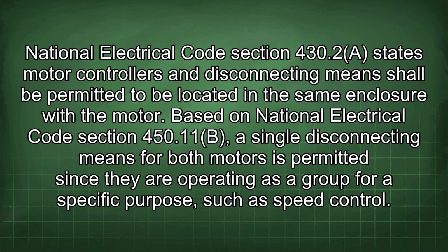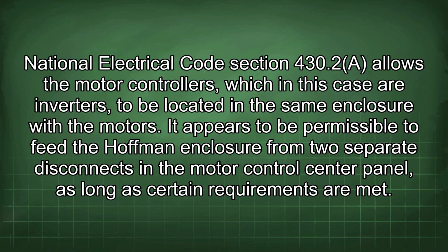National Electrical Code Section 430.2(A) states motor controllers and disconnecting means shall be permitted to be located in the same enclosure with the motor. Based on National Electrical Code Section 450.11(B), a single disconnecting means for both motors is permitted since they are operating as a group for a specific purpose, such as speed control. National Electrical Code Section 430.2 allows the motor controllers, which in this case are inverters, to be located in the same enclosure with the motors.